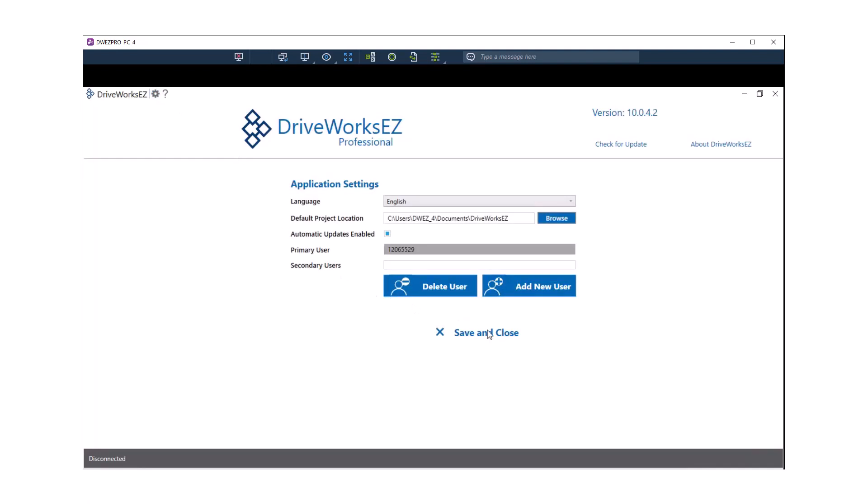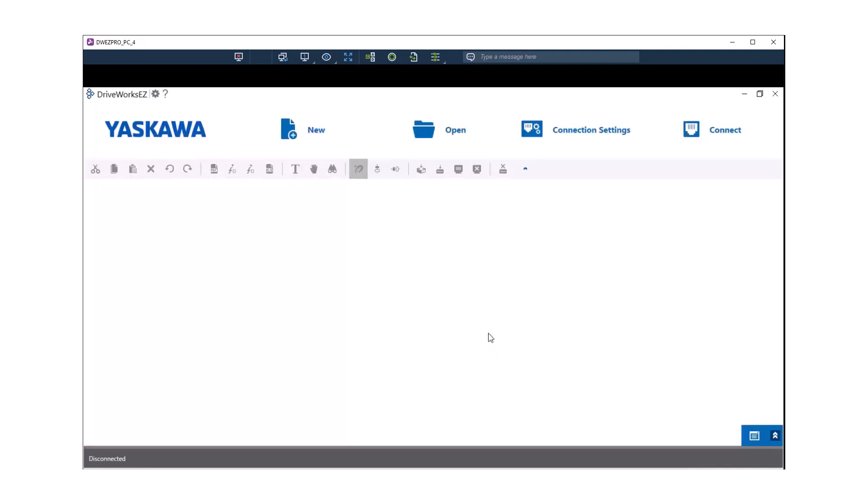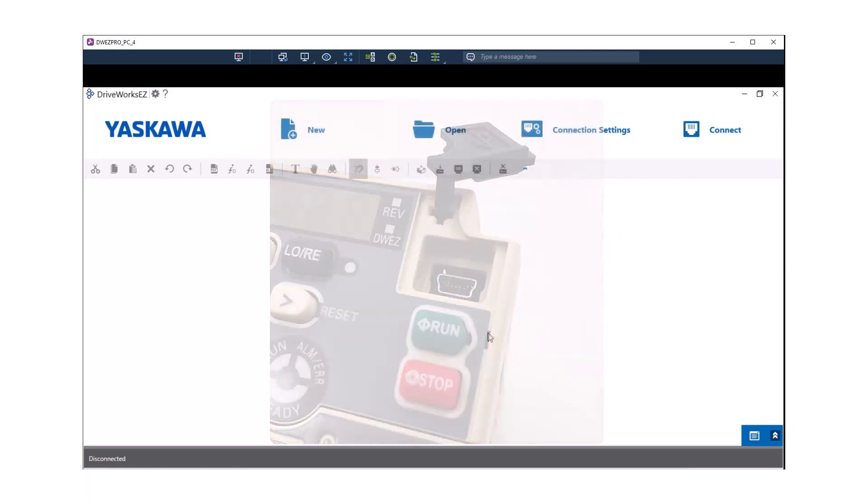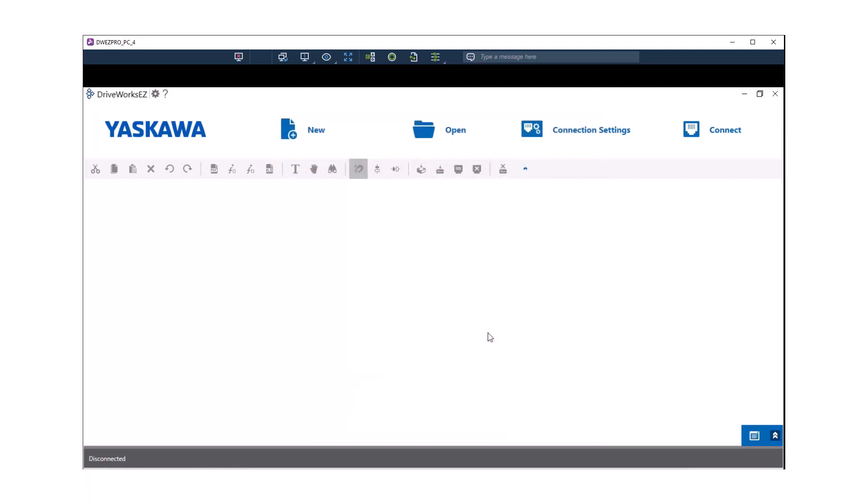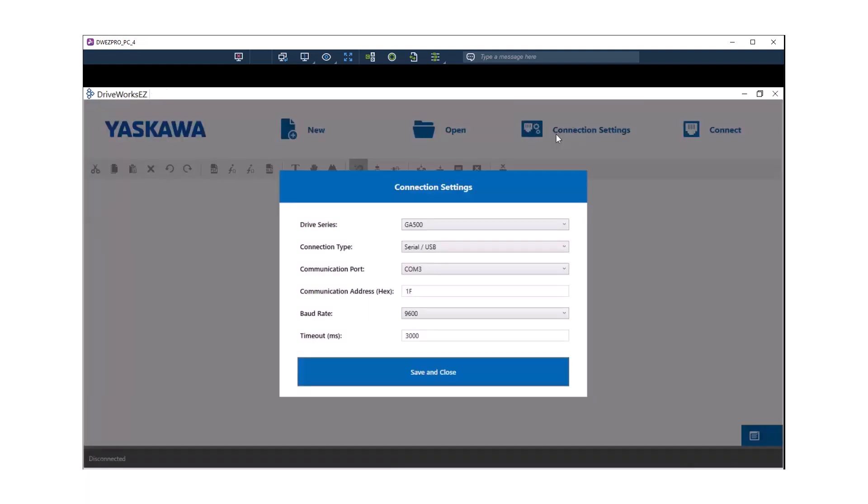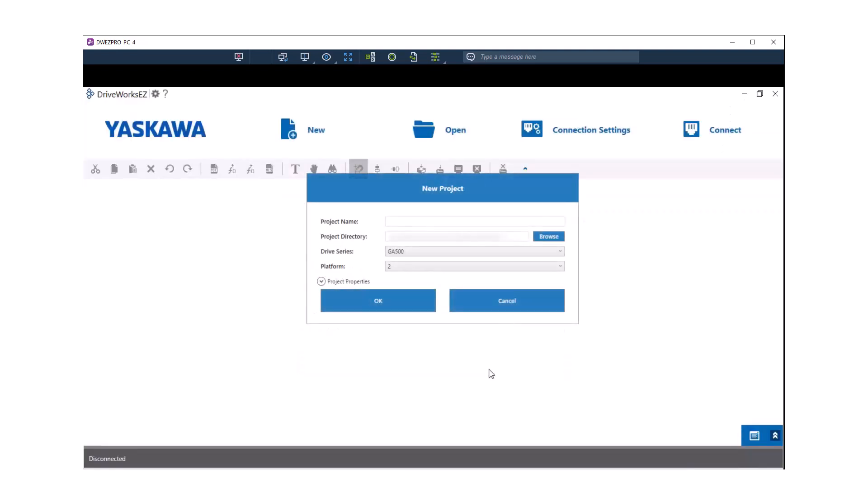Since we are using this remote PC now, there are a few things we need to be aware of. This remote PC is locally connected via a USB connection to a GA500 drive. So when you are using DriveWorks EZ Pro through the Splashtop software, make sure that you select a USB connection and when you start a DriveWorks EZ 10 project, make sure you select a GA500 drive.